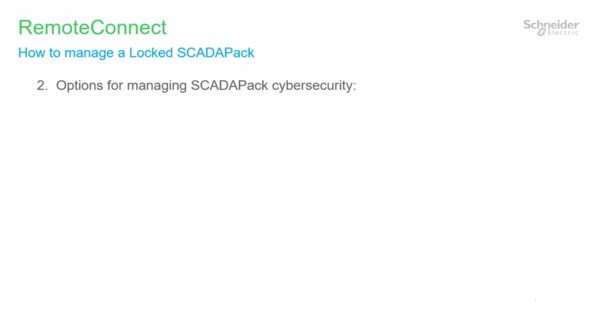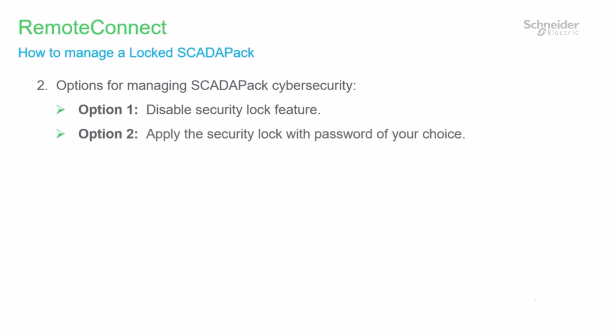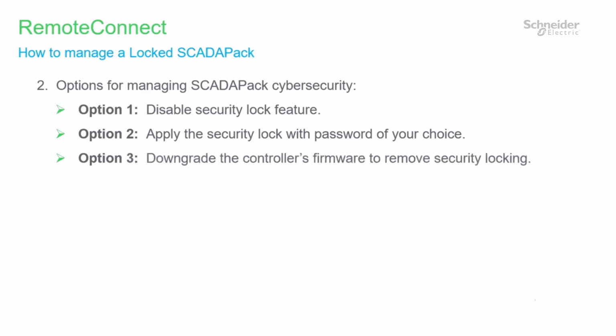Once updated to RemoteConnect 3.6.3 or newer, you will have three choices for managing the secure lock on your new SCADAPack. Option 1, disable the security lock feature. And if security lock is desired in the future, a cold boot or a service boot will re-enable it. Option 2, apply the security lock with a password of your choice. Option 3, downgrade the controller's firmware to remove security locking altogether.